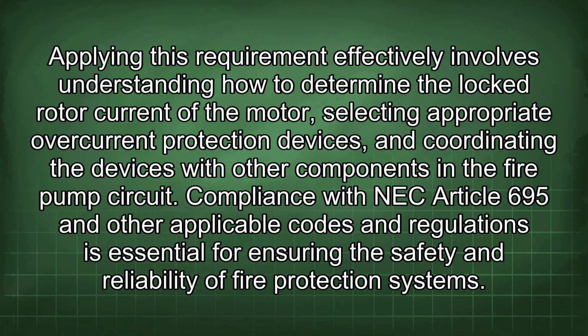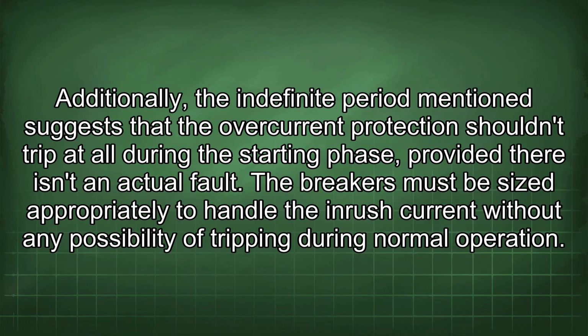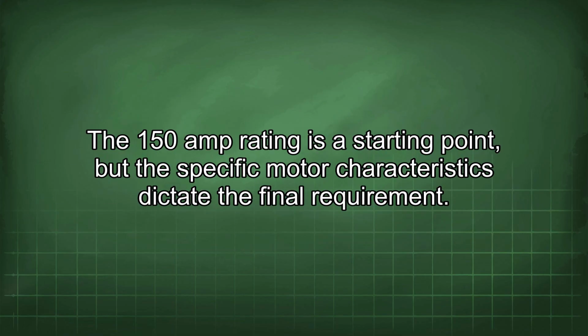Additionally, the indefinite period mentioned suggests that the overcurrent protection shouldn't trip at all during the starting phase, provided that there isn't an actual fault. The breakers must be sized appropriately to handle the inrush current without any possibility of tripping during normal operation. The 150 amp rating is a starting point, but the specific motor characteristics dictate the final requirement.